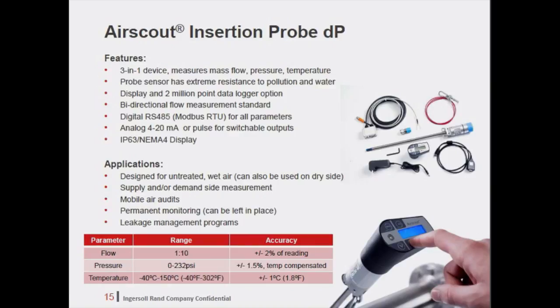The Airscout Insertion Probe DP is also a 400 mm probe with the capabilities to measure mass flow, pressure, and temperature, along with bidirectional flow measurement as a standard feature. The same digital display with 2 million data point logger or a connector cap with the digital and analog communication options can be used with the probe. The DP probe sensor has an extreme resistance to pollution and water, which is ideal for supply-side measurement, whether it be temporary installation with air audits or that permanent installation.